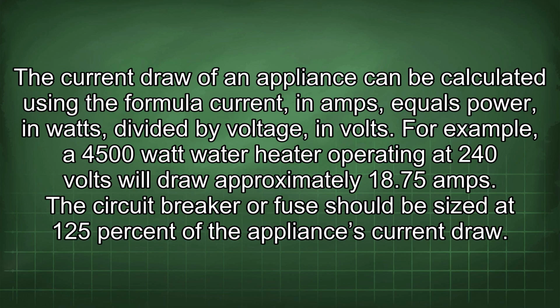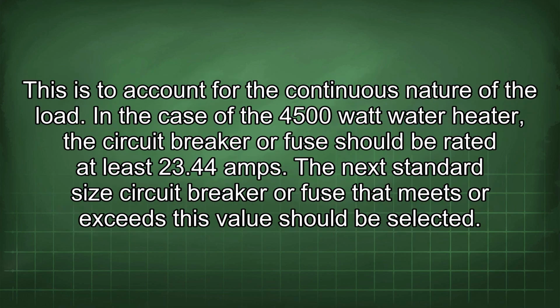The current draw of an appliance can be calculated using the formula current in amps equals power in watts divided by voltage in volts. For example, a 4,500 watt water heater operating at 240 volts will draw approximately 18.75 amps. The circuit breaker or fuse should be sized at 125% of the appliance's current draw. This is to account for the continuous nature of the load.